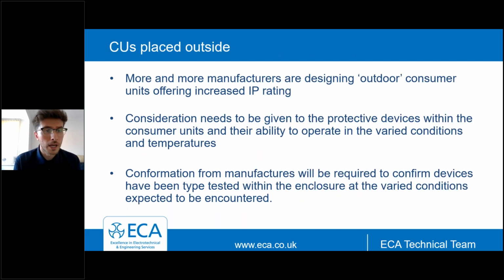So the last point we're going to look at is consumer units placed outside, and unfortunately no image for this one. We're seeing more and more manufacturers designing outdoor consumer units that offer an increased IP rating. With this one, consideration needs to be given to the protective devices housed within that enclosure, and their ability to operate in the varied conditions and temperatures. So we've got to think about the seasonal changes, the weather changes, the different times of year. It's not just the IP rating we need to consider, it's the effects on the devices that are housed within that enclosure.